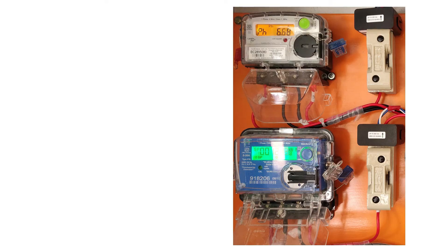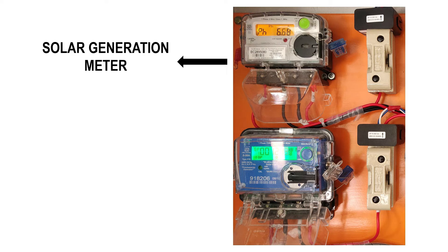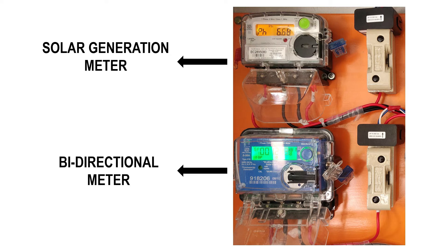In a typical rooftop solar system, there are generally two meters installed in your energy panel: a solar generation meter which records only the solar generation, and a bi-directional meter which records both the import and export of energy. The bi-directional meter is the one used by DISCOMs for billing.